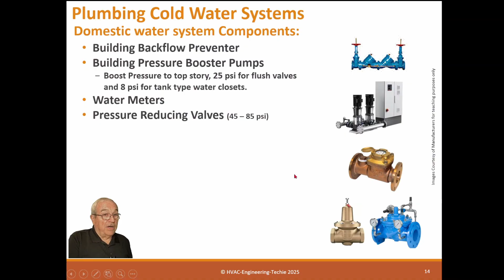Reduced pressure valves, in case you have too much pressure. Municipalities are required to give you at least 45 psi, but I've seen as high as 125 psi, depending on the control system they have for municipal water. Again, if they have staged pumps, it might bounce around a lot. Or, which is more troubling, when they put a pumper truck on it, and it may actually overpressure the water line. So sometimes you do require pressure reducing valves. Pressure reducing valves are normally 45 to 85 psi.